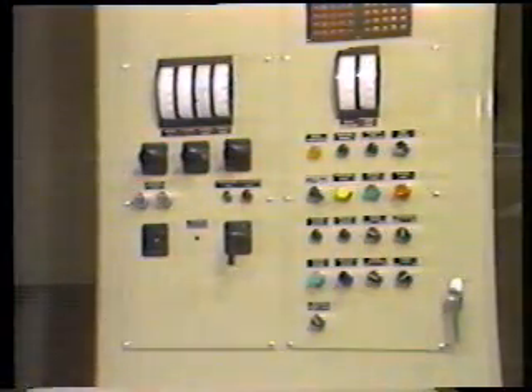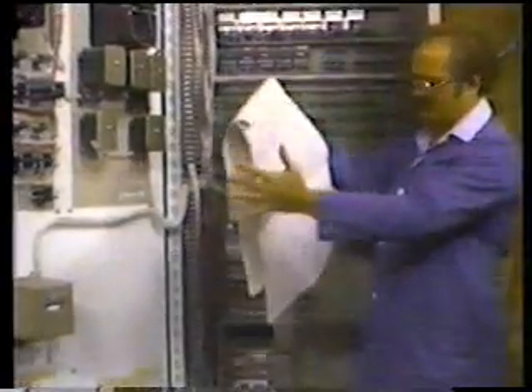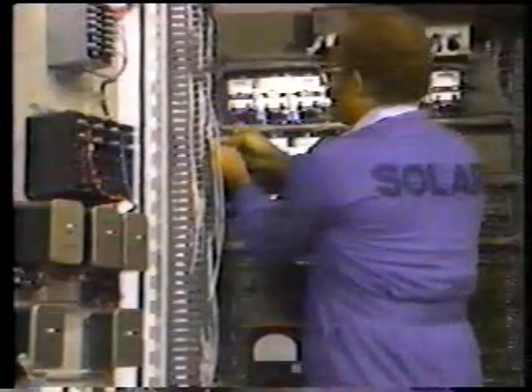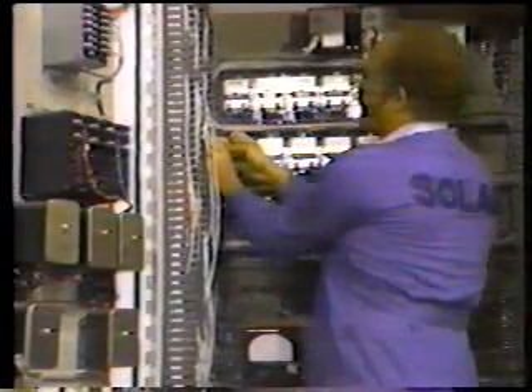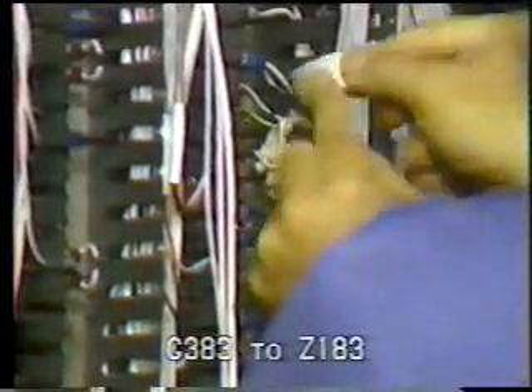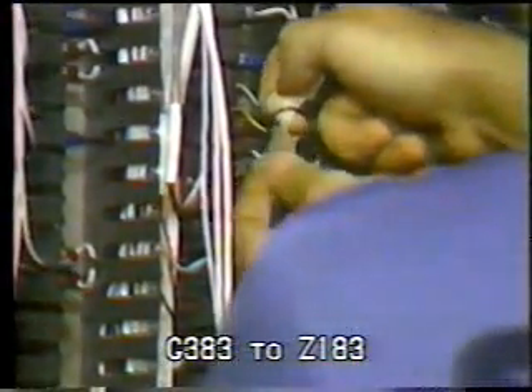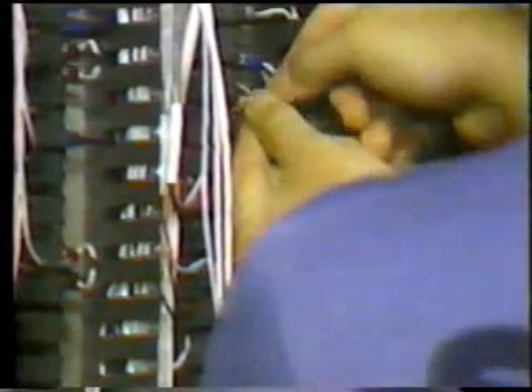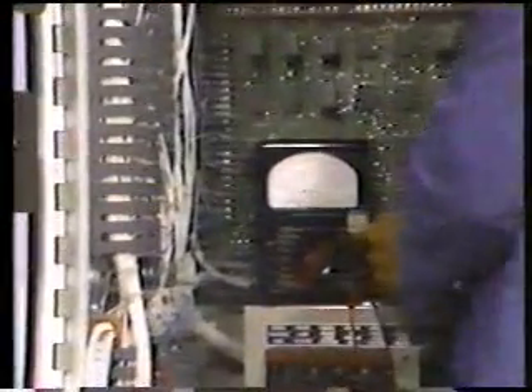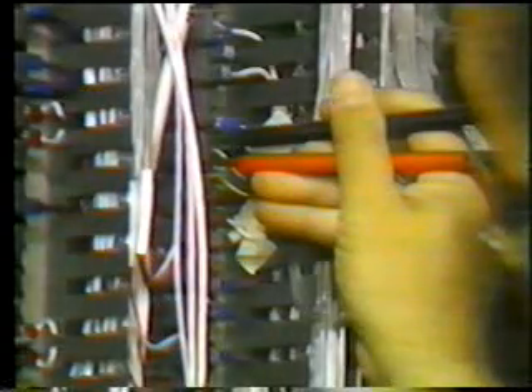Voltage output must be checked when the engine is operating at 100% speed. Determine the wire numbers and terminal connections in the control panel, the pickup, by checking the schematic. For C383, find the leads going to engine speed monitor Z183 and tag them. Next, set the multimeter to the 300-volt AC scale. Connect the two leads from the multimeter in parallel to the lead from the magnetic pickup, connecting one lead to each wire.